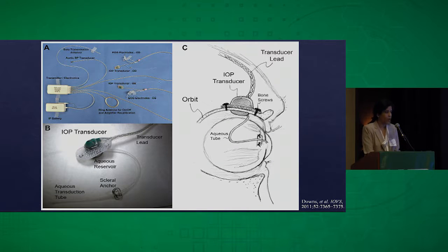At the UAB Center for Ocular Biomechanics, we address this critical barrier in understanding the true character of intraocular pressure and ocular perfusion pressure by developing this fully implantable radiotelemetry system. This system allows bilateral measurements, and it's fully implantable.